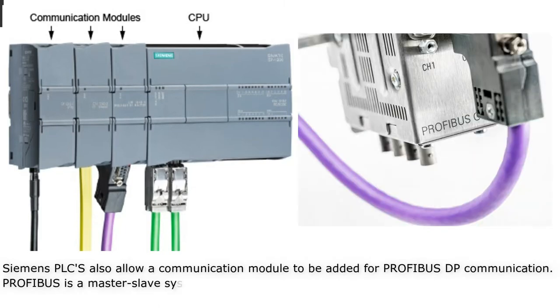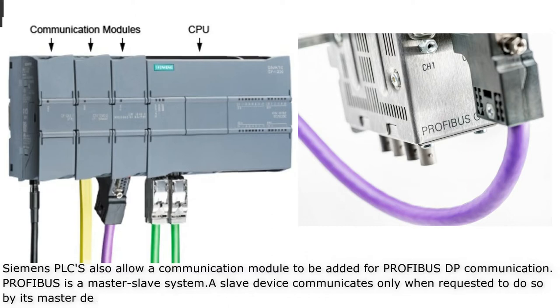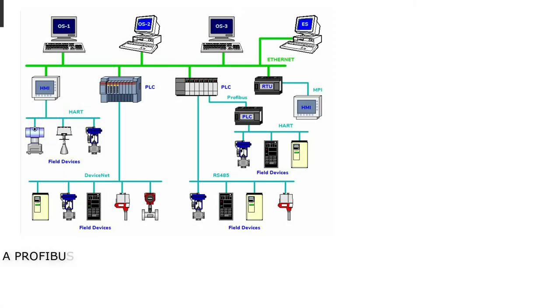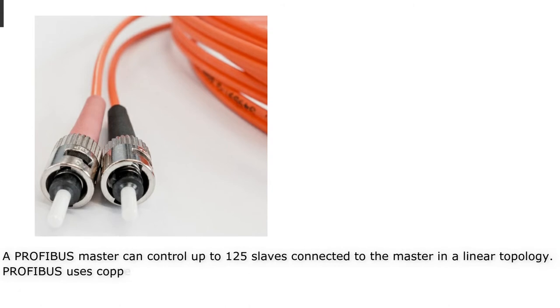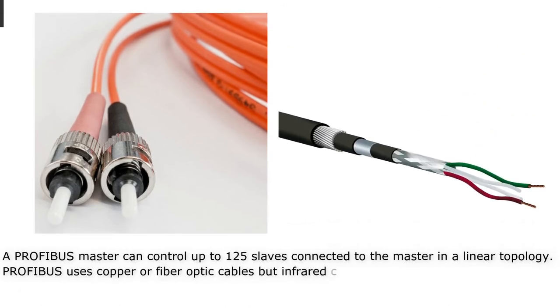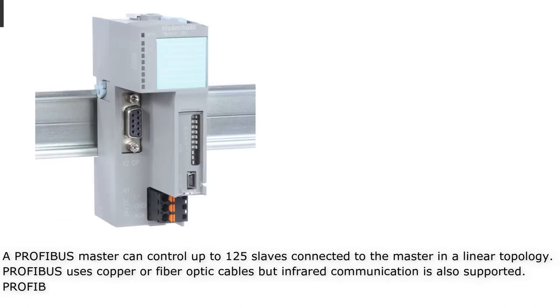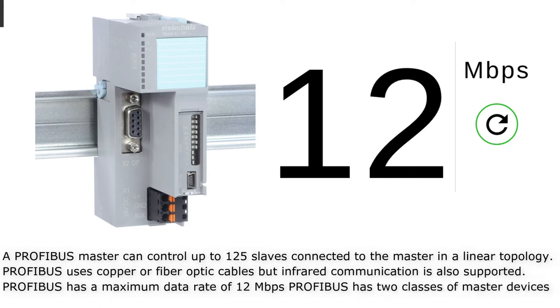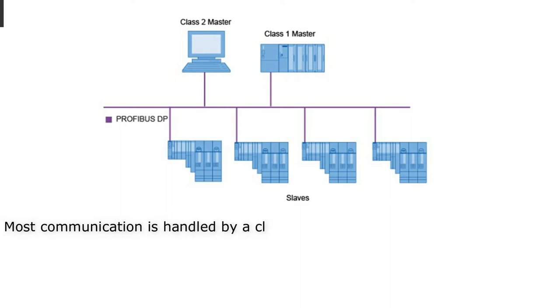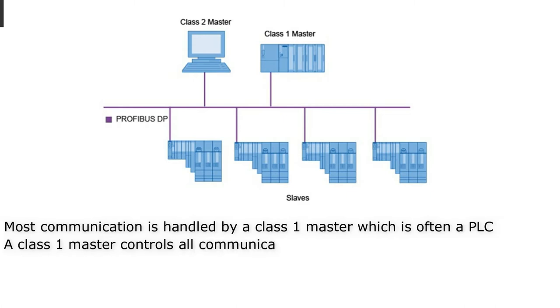Profibus is a master-slave system; a slave device communicates only when requested by its master device. A Profibus master can control up to 125 slaves connected in a linear topology. Profibus uses copper or fiber optic cables, but infrared communication is also supported. Profibus has a maximum data rate of 12 Mbps. Profibus has two classes of master devices. Most communication is handled by a class 1 master, which is often a PLC that controls all communication with its slaves.